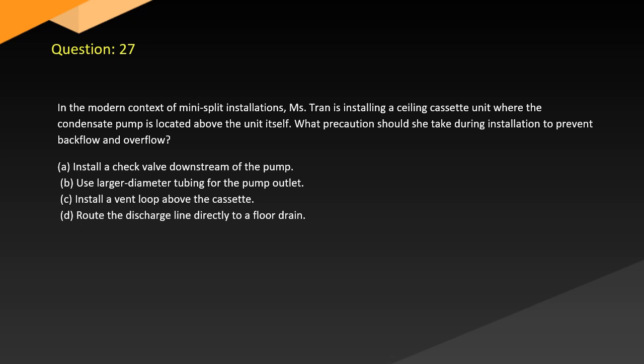Question 27. In a modern context of mini-split installations, Tran is installing a ceiling cassette unit where the condensate pump is located above the unit itself. What precautions should she take during installation to prevent backflow and overflow? A. Install a check valve downstream of the pump. B. Use larger diameter tubing for the pump outlet. C. Install a vent loop above the cassette. D. Route the discharge line directly to a floor drain.